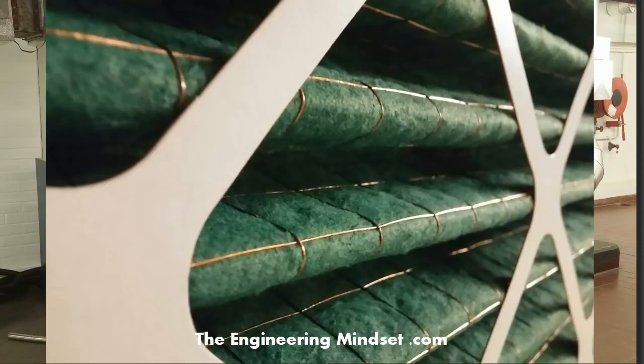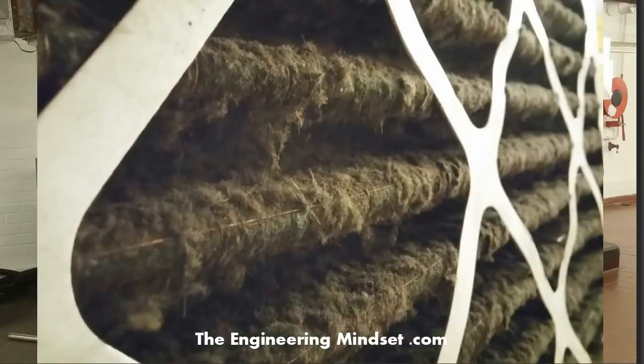Looks quite nice. And then a few months later, after maybe a few days, it depends where your building is. If it's sucking air off of the motorway, next to an industrial site, or maybe near a coal power station or something, you're going to be going through a lot of filters. So this is what the dirty filter looks like, only after a few weeks, a few months.